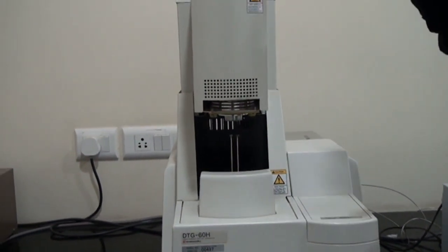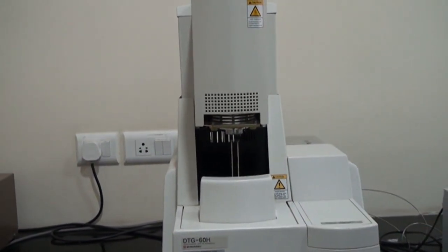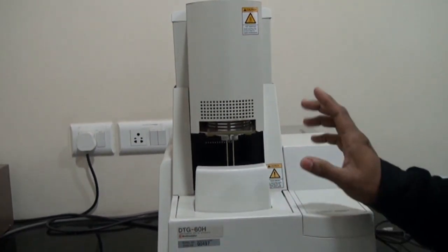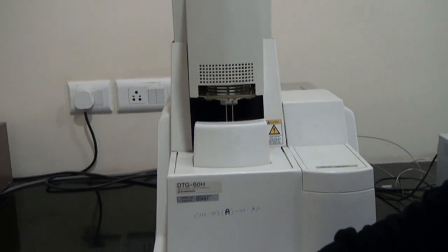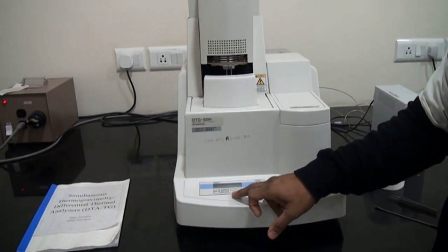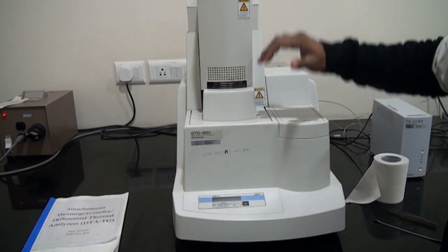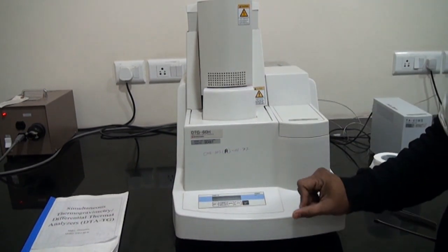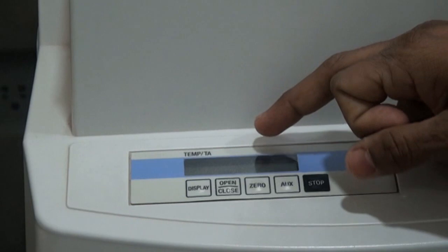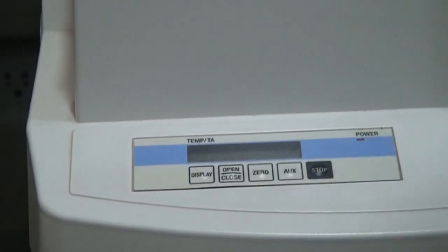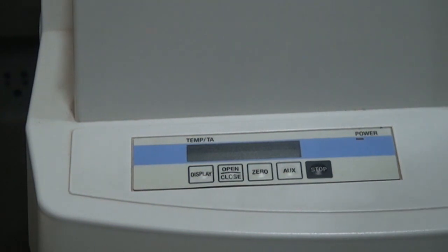So the furnace will be closed. Keep in mind, when it is opening and when it is closing, you cannot use any function key buttons. Even if you press, it won't operate until it's completely closed or perfectly open.